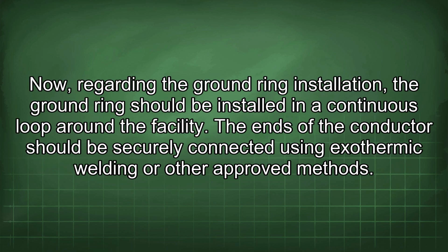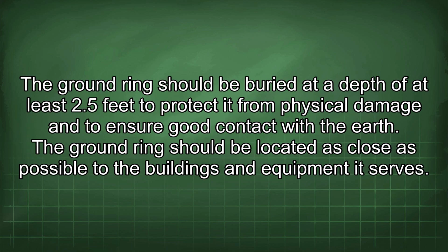Now, regarding the ground ring installation, the ground ring should be installed in a continuous loop around the facility. The ends of the conductor should be securely connected using exothermic welding or other approved methods. The ground ring should be buried at a depth of at least 2.5 feet to protect it from physical damage and to ensure good contact with the earth.